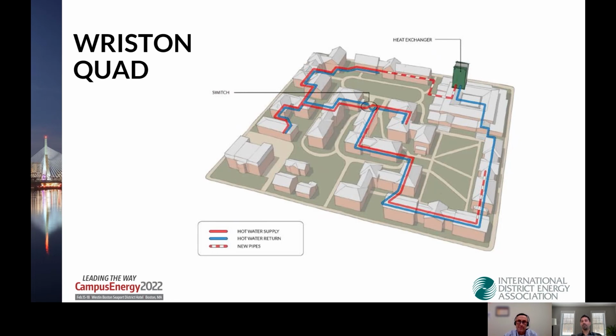So that unlocked our ability to transfer from steam distribution to hot water distribution in only one summer. So as David mentioned, yes, we have to remove all these heat exchangers and replace them with a valve, but we didn't have to install feet and feet of piping, just those two little sections at the start of the loop and at the end of the loop, so we could complete our inverted return.